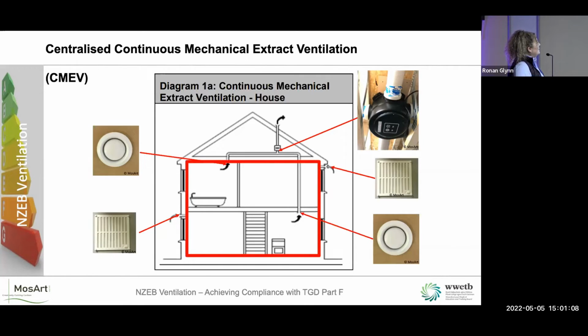Our airtight, continuous vapor control layer is on the inside, the warm side of our insulation. We're assuming here that it's insulated at ceiling level. Every time you have a diffuser coming down into your wet rooms, you're breaching this airtight membrane, which means you have to think about how you're going to seal that up. Have I got tapes and membranes to do that? We're also dragging warm air, this is all, we'll say, a 20 degree space, up into the cold space in the attic. So now we have an issue of condensation.